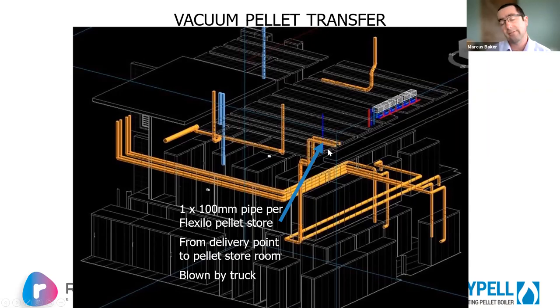It'll be a little bit less than full, so that all the pellets in the pipework can be blown out. And so just to be really clear, there will not be pellets in this pipe when the delivery ceases. So the truck turns up, their first job will be to blow air through the pipe, and then they'll turn on the delivery mechanism and pellets will be blown through. And then they'll turn off the delivery mechanism, but continue blowing air through. So all of this is voided of pellets. And that will be 100 mil metal pipe that's all fixed in place and hidden in walls, et cetera.